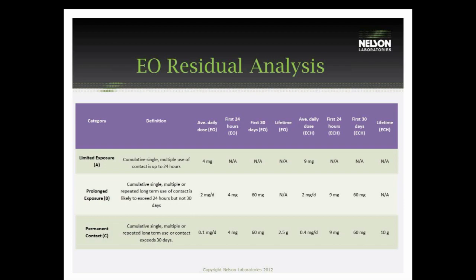There are specific EO residual levels that are allowable on the device, dependent upon which type of device it is. For a limited use device, the most EO you can have on the device is 4 milligrams, determined based on a worst-case situation for how long the device will be in contact with the patient. We recommend for limited use devices that they are tested for three times the expected patient contact time to simulate a worst case. For EO that is 4 milligrams allowed, and for ECH 9 milligrams. We also test for ethylene glycol, though the standard does not have set limits for that.